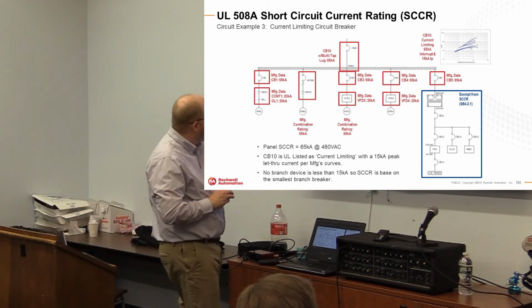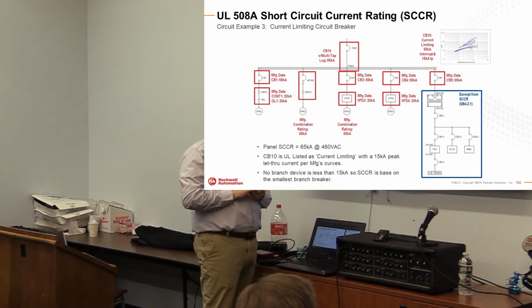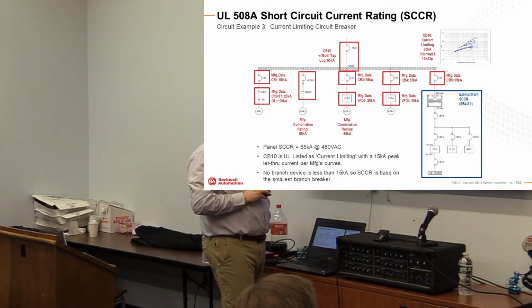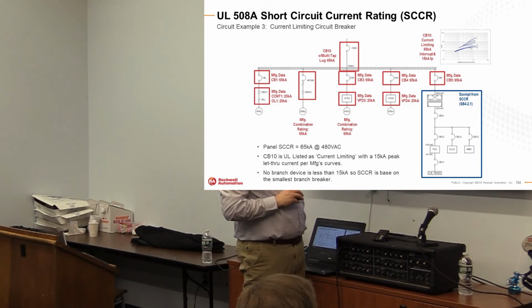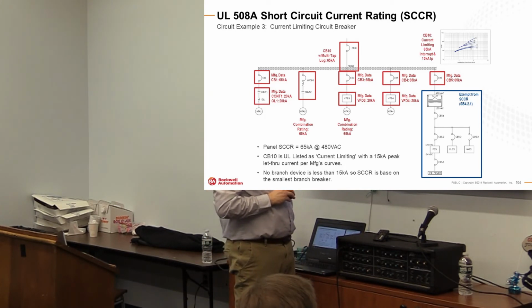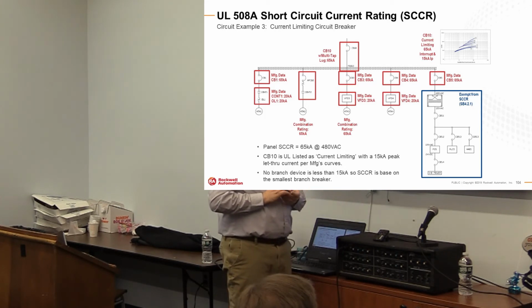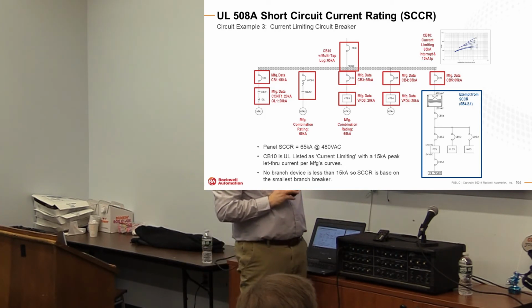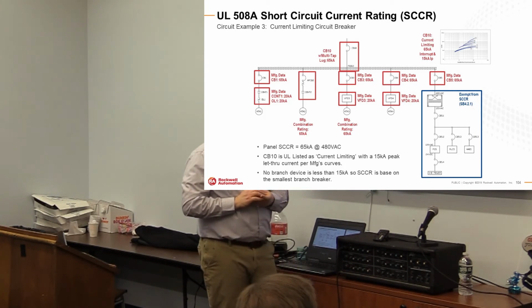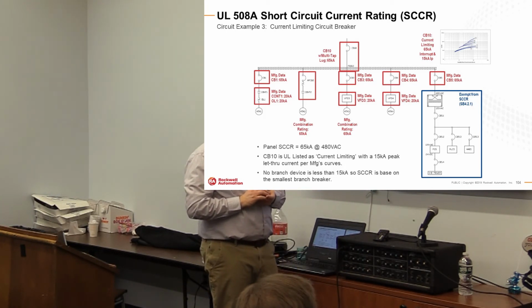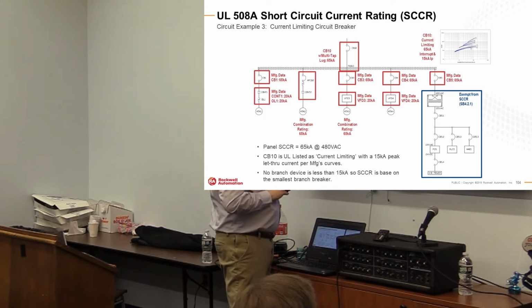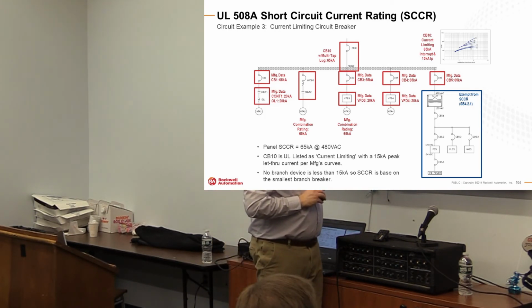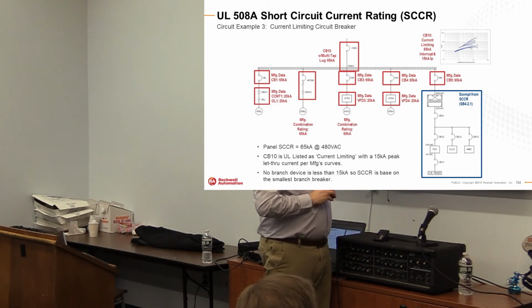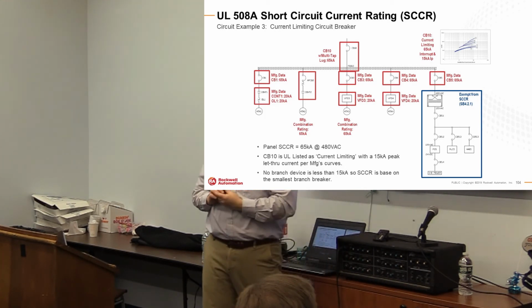Well, the one here for circuit number 1, we got 20,000, so yes. We have a combo rating, so that's good there. We have another combo rating of 65, but the VFD there is 20 kA. We have a 20 kA drive rating. So in this particular case, all of the downstream devices are as good or better than 15. We then go one notch upstream and see all of the interrupt ratings match what the feeder is, and so we can claim 65.